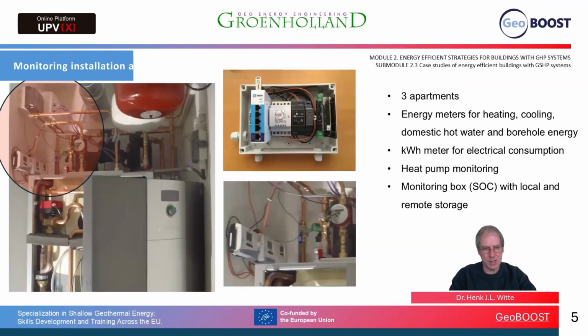On the heat pump system side, we have 3 energy meters installed. You can see that on the left. 3 energy meters measuring the heat and cool delivered to the apartment, the domestic hot water being used by the apartment, and the heat and cool extracted from the ground. We also have an electrical kilowatt-hour meter in the heat pump to measure the electrical consumption of the compressor and the electrical consumption of the borehole pump.